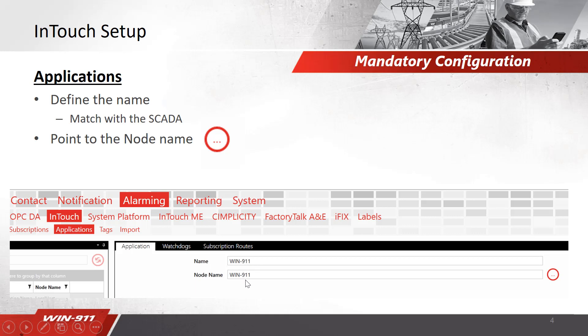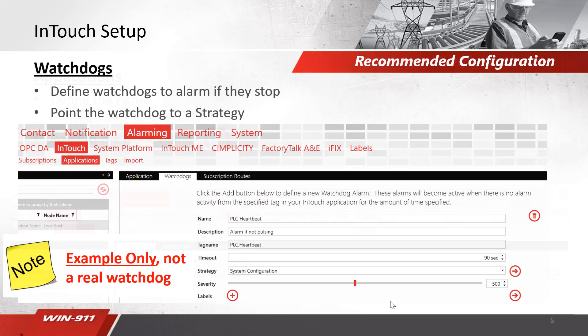We also have a node name — you can point to your node using the ellipses there. The next is a recommended step: using watchdogs. You can configure something such as a PLC heartbeat or some kind of state alarm. You're still in the Applications tab under Watchdogs. Here you can assign a name — I'm using a PLC heartbeat. You need a description and the tag name. From there you can set the timeout and a strategy. This strategy will point to a tactic or call list. If you're not familiar with tactics and strategies, please go back and watch our how-to instructional videos.